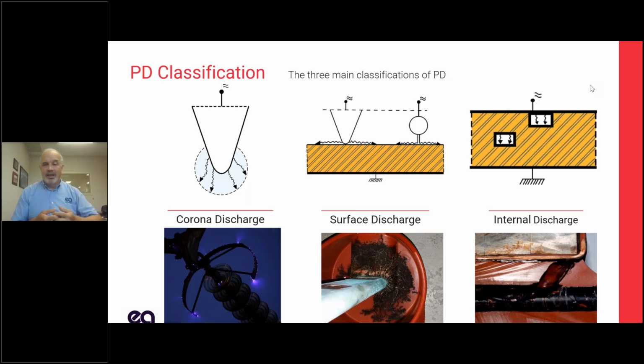It's the hardest to find in that it doesn't generate certain side effects, and there's nothing to see. You can do an inspection, you can tear it apart, but until you actually cut down and find the void in the insulator, you're not going to see anything at all. So visual inspection is of no use for internal discharge. So we've got these three types. We're going to talk a little bit more about them.